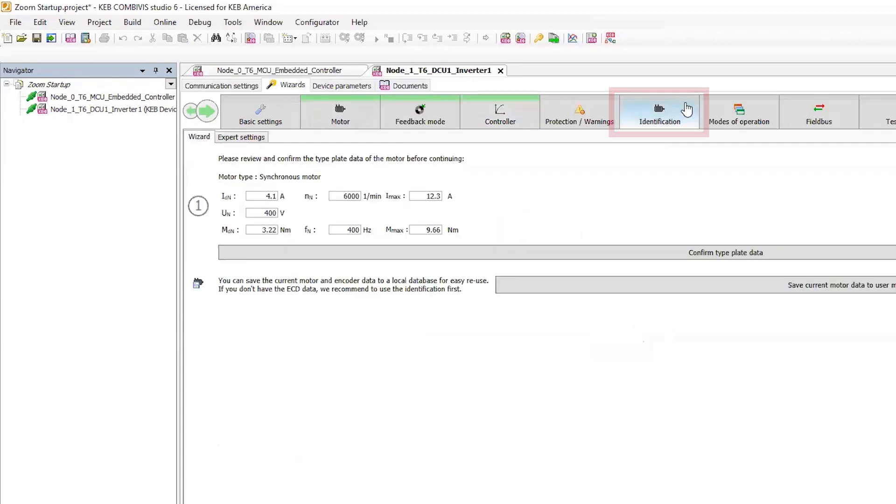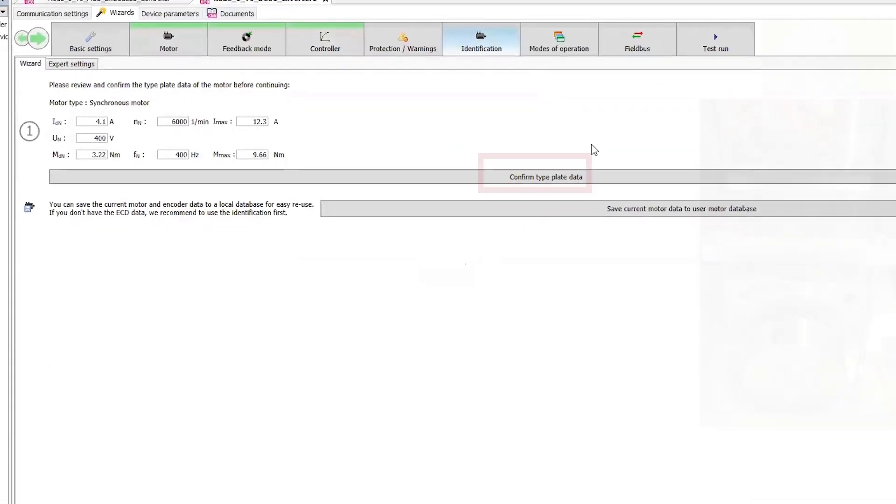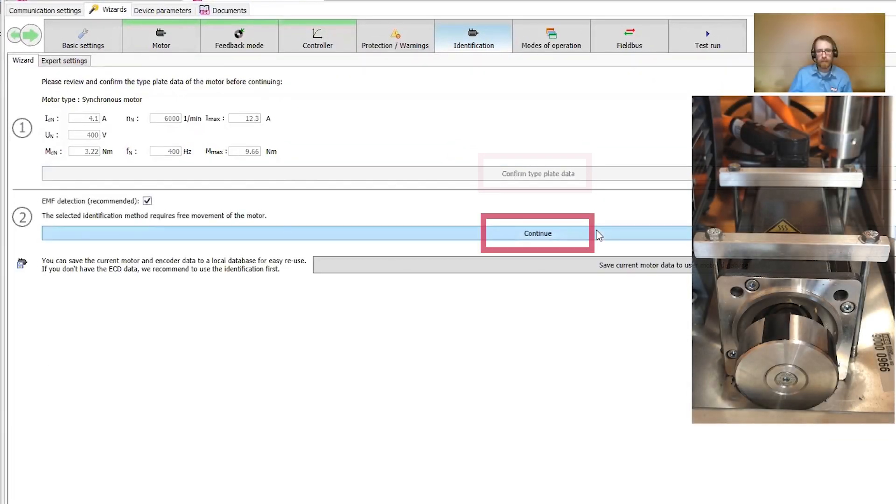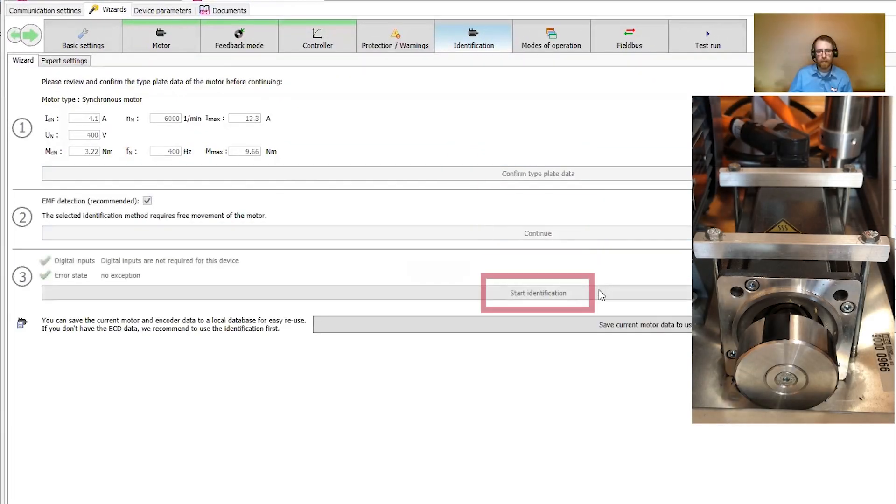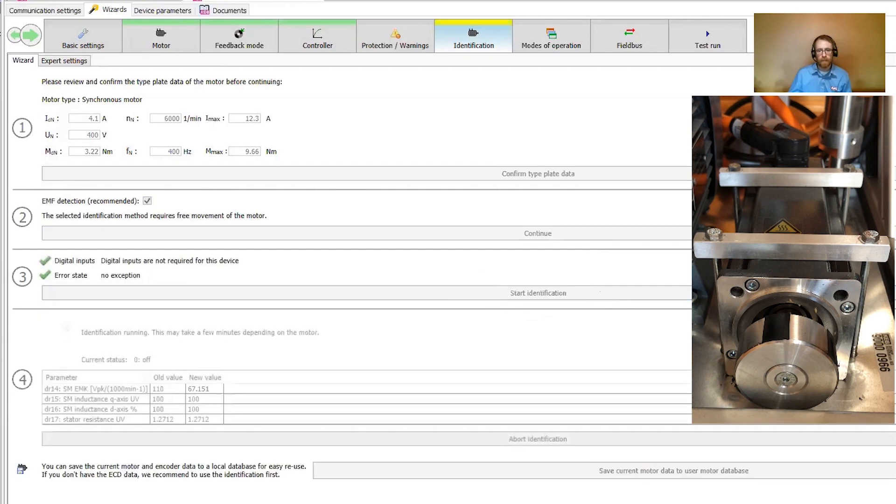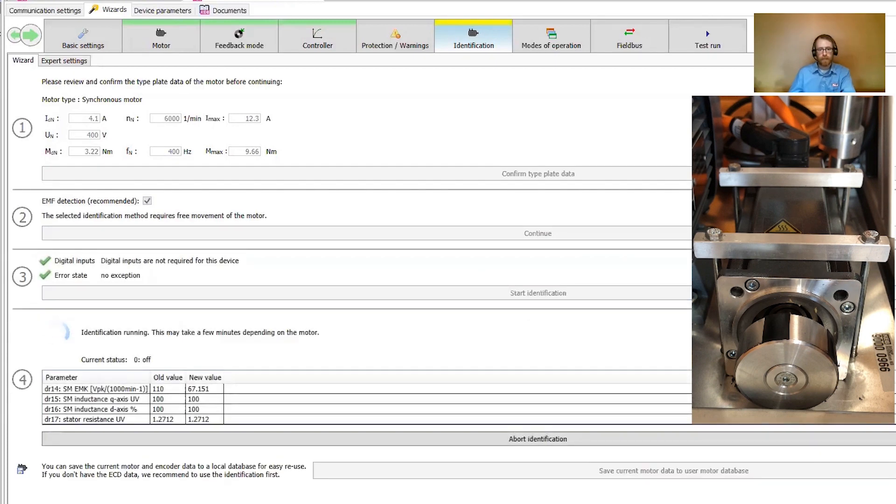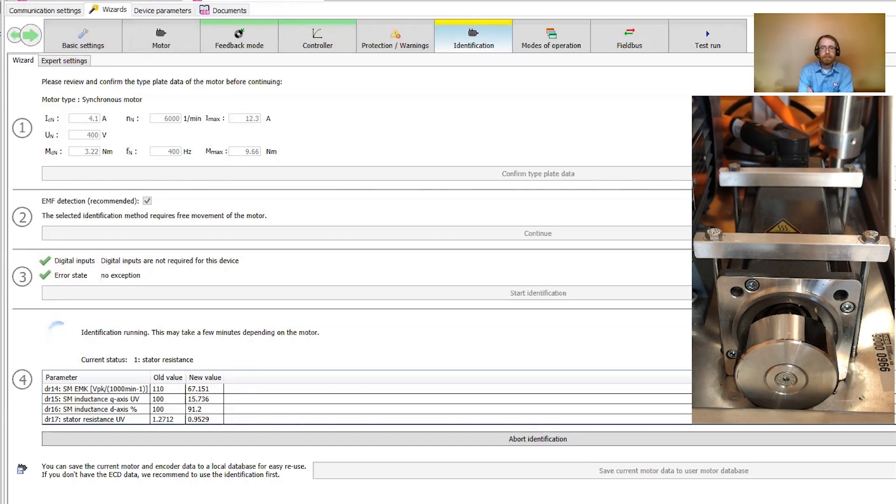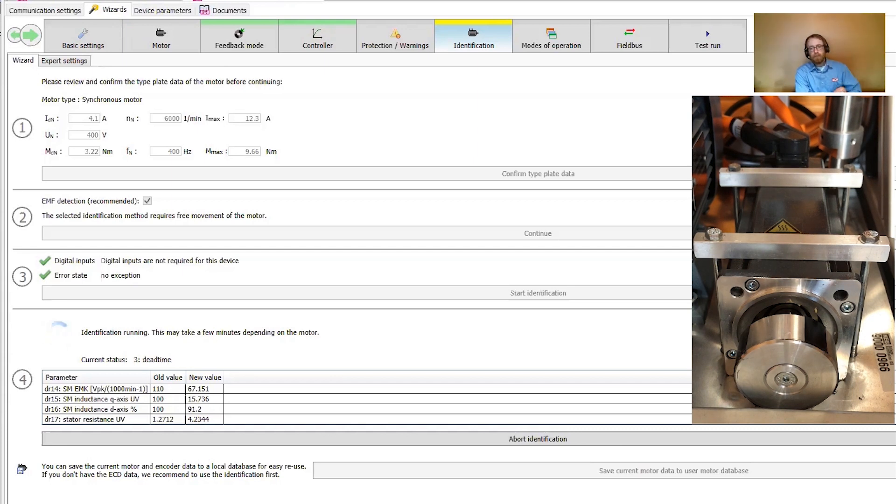In the identification tab, I'll just follow through the steps to start the motor learn process. Then give the hardware enable to initiate the motor learn. You can hear the process has started and will typically take two to three minutes. So I'll fast forward through this part since there isn't much to see.